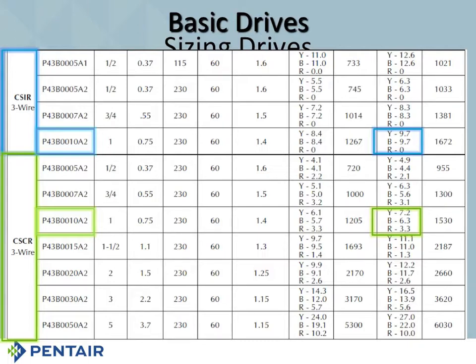Now, again, the other thing that's really important to note there is if you add black and red together, they don't equal yellow. And that's something that usually people are going, well, how come it's not equal? And the answer is because the amperage going down that red wire has been boosted by a starting capacitor. So you're not putting all that amperage in there. It's just a boost, so it goes away. Your real amperage is going to be the subtraction of yellow and black, which is in this case 0.9 amps. So you've got 0.9 amps going into that red, but you've got 3.3 going down because you're using a running capacitor to boost that 0.9 amps up. All right?